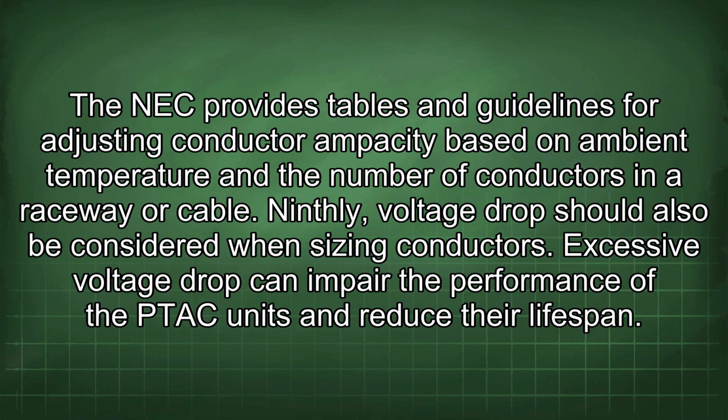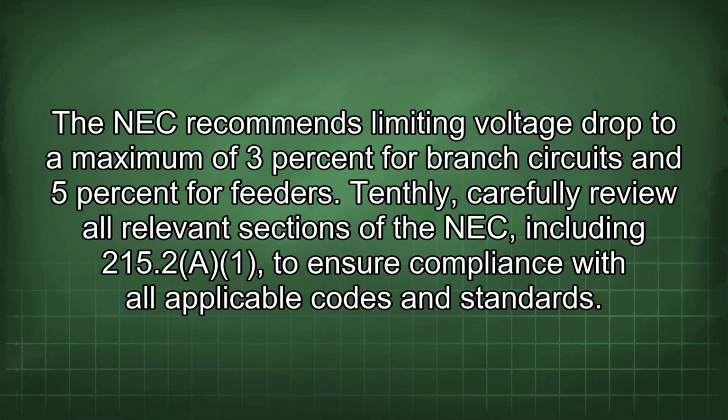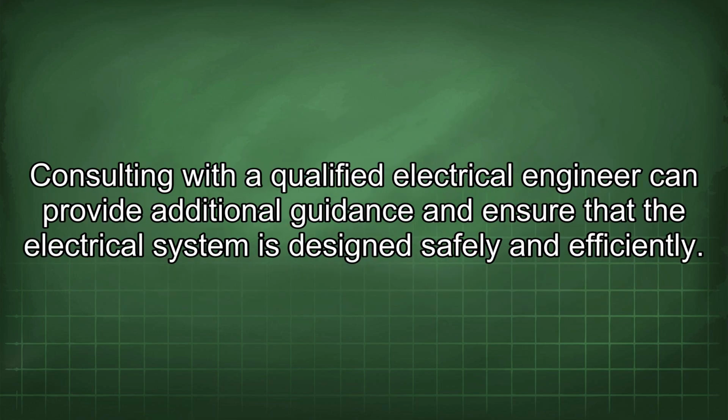Excessive voltage drop can impair the performance of the PTAC units and reduce their lifespan. The NEC recommends limiting voltage drop to a maximum of 3% for branch circuits and 5% for feeders. Tenthly, carefully review all relevant sections of the NEC, including 215.2(A), to ensure compliance with all applicable codes and standards. Consulting with a qualified electrical engineer can provide additional guidance and ensure that the electrical system is designed safely and efficiently.